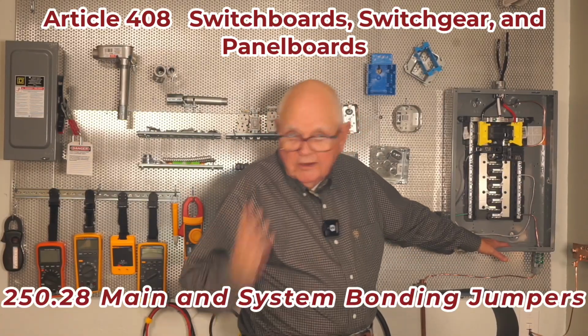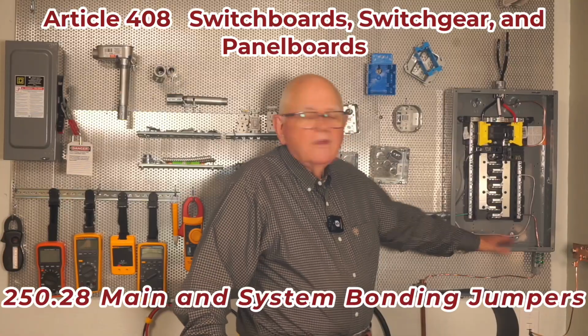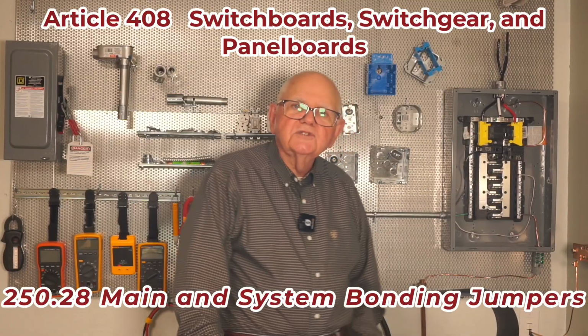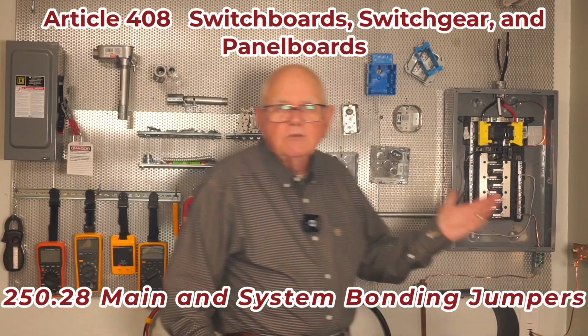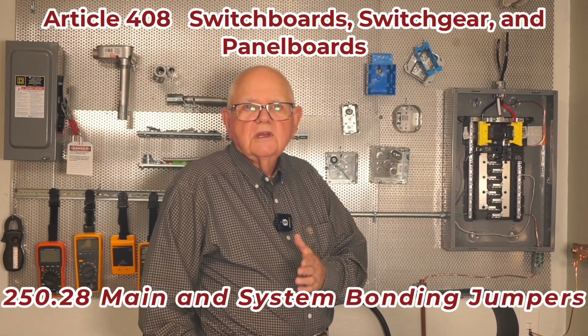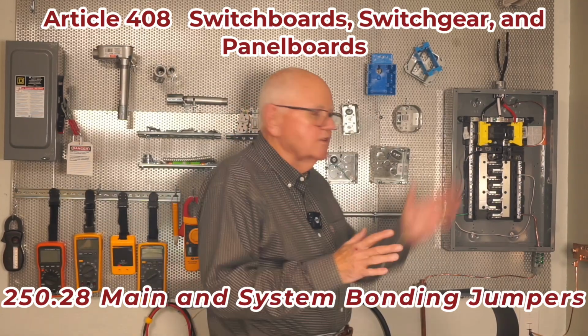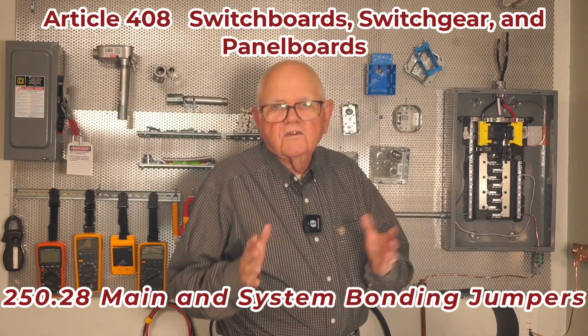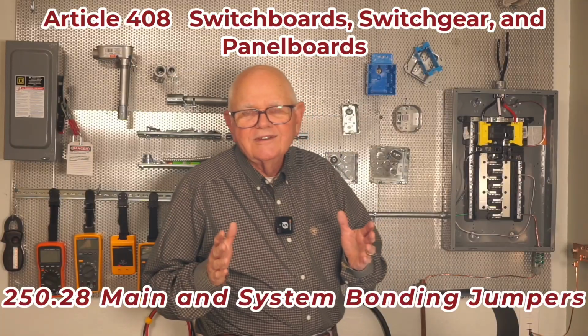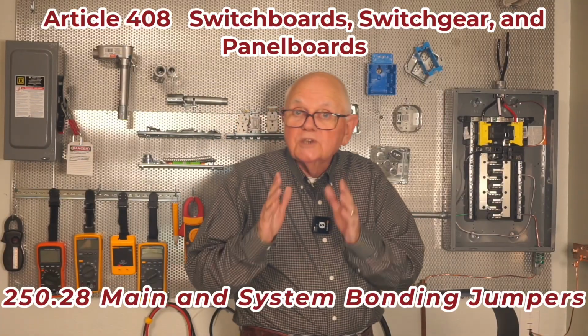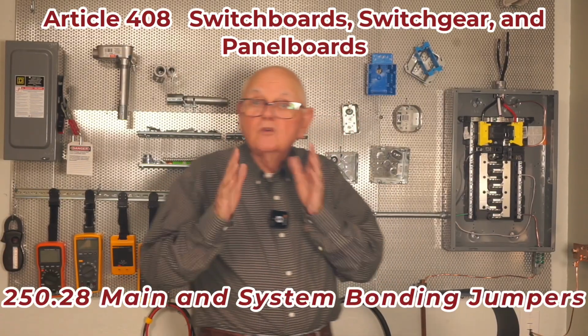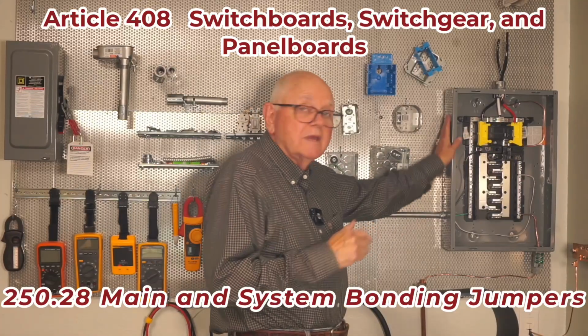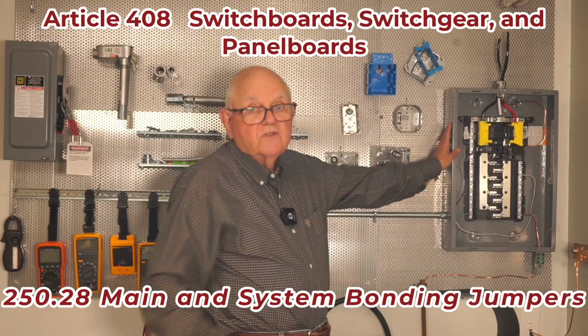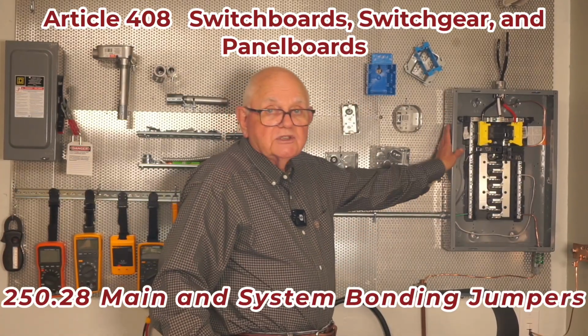Now, on grounding and bonding. If this is being fed from a separately derived system, it's not a service anymore. In that case, we don't call that green screw the main bonding jumper. It's the system bonding jumper. Righty? Now, where we run into problems is when people go to a sub panel. Now this is being fed maybe from my main panel upstream, wherever it is. This becomes a sub panel.